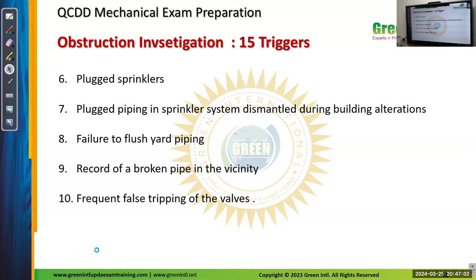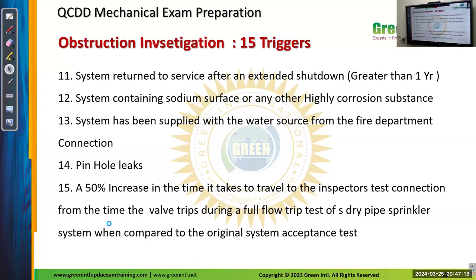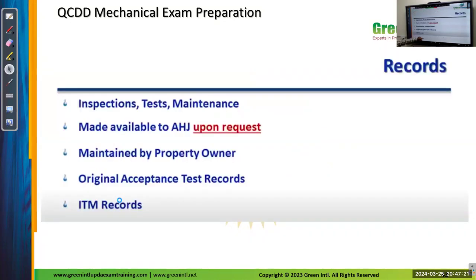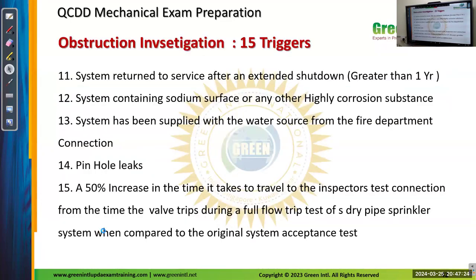Plugged piping of sprinkler systems dismantled during building alterations. Failure to flush yard piping. Record of a broken pipe in the vicinity. Frequent false tripping of the valves. So this is like a checklist. They will check whether these defects are present or not. Okay. So, a 50% increase in the time it takes for water to travel to the inspector's test connection from the time of valve trips during a full flow trip test of a dry pipe sprinkler system when compared to the original system acceptance.